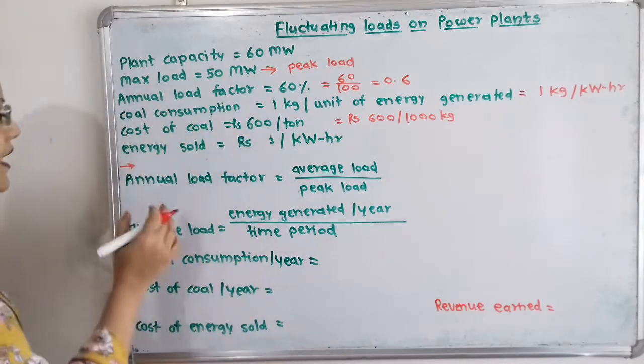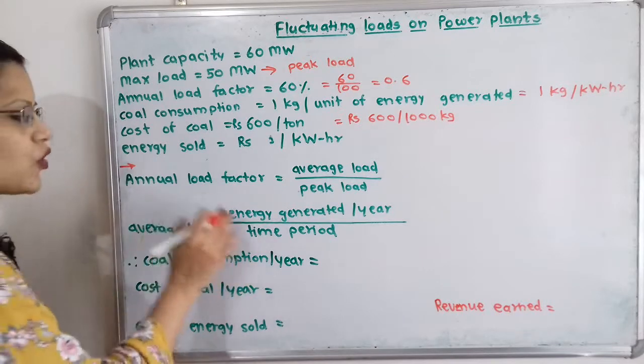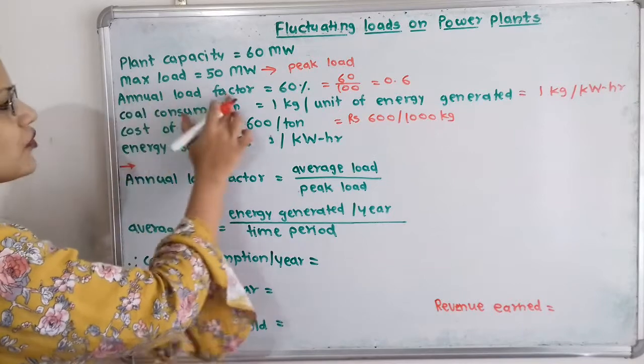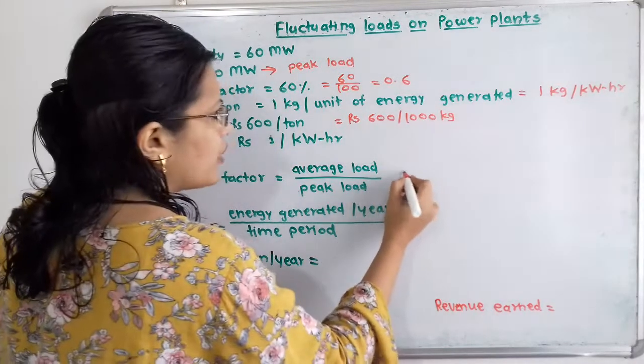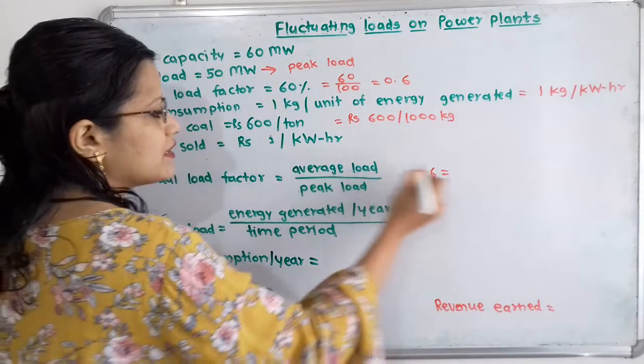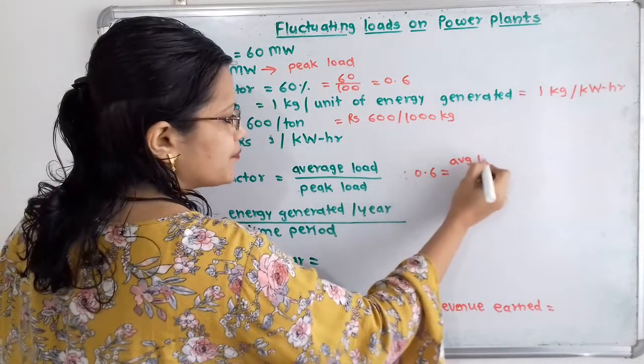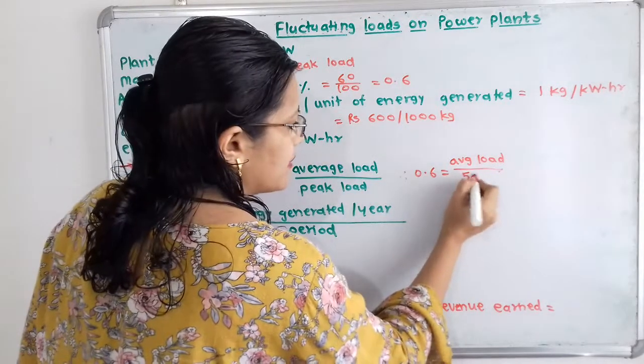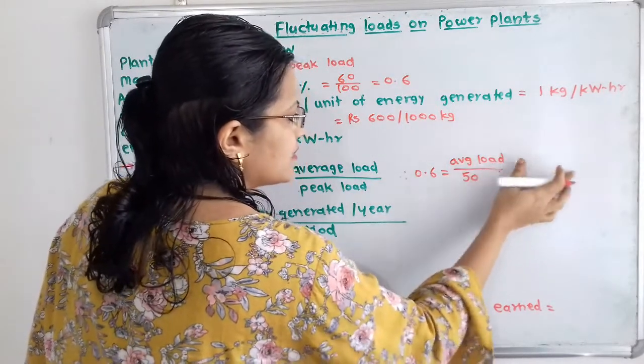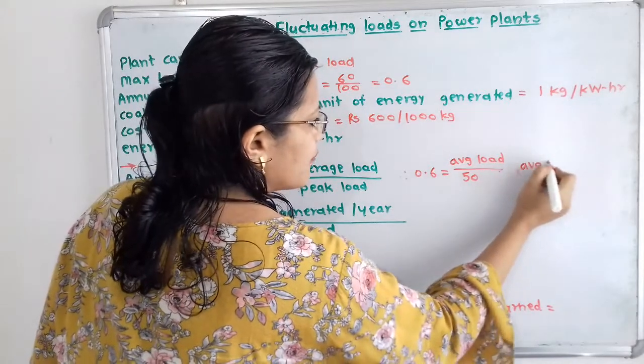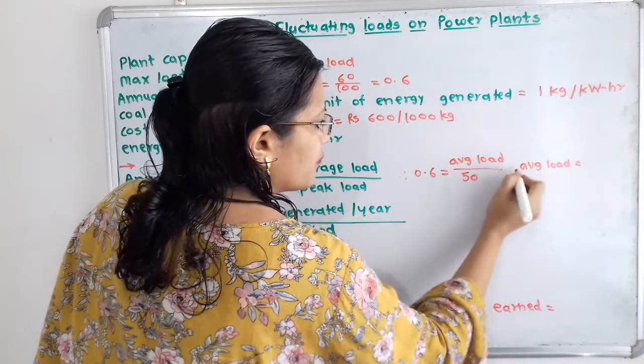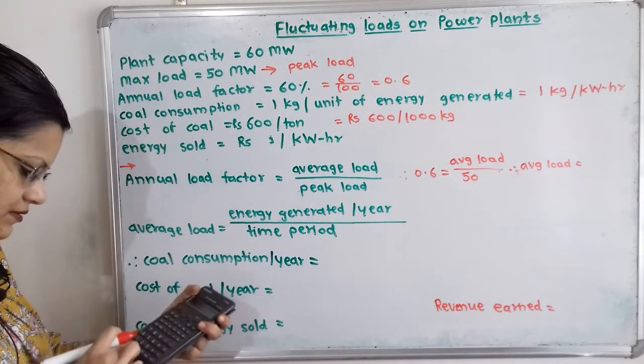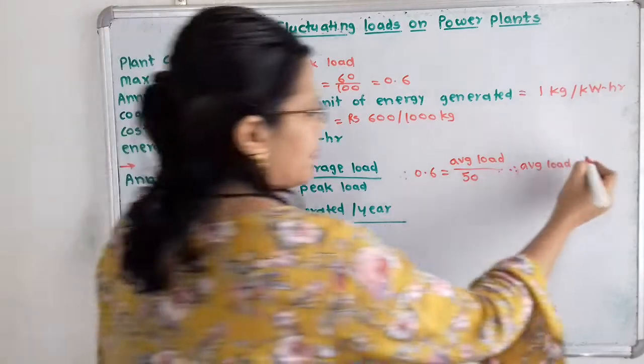From the given data, annual load factor is nothing but average load divided by peak load. So 0.6 equals average load divided by peak load of 50 megawatt. Therefore, average load is equal to 50 multiplied by 0.6, which is 30 megawatt.